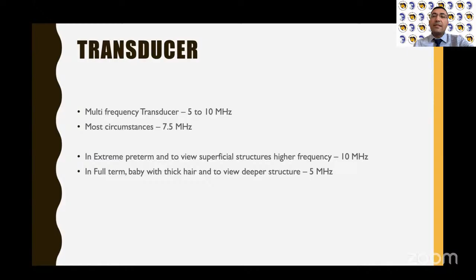What kind of transducer do we use? There are various kinds like sectoral, linear, curvilinear, or array. But what we use is the sectoral, that is the commonest. The reason is that it is usually used in echocardiography, which is primarily why we are purchasing the ultrasound machine. So from the same probe, we can do the brain ultrasound also. We need not have multiple probes because they are very costly. But if we can afford it, then we can have a linear probe also, which can get a better image for our head ultrasound.